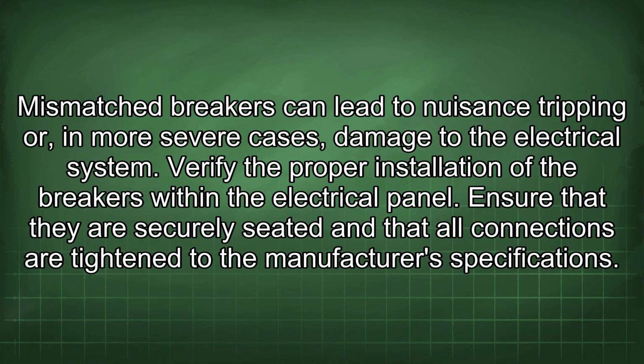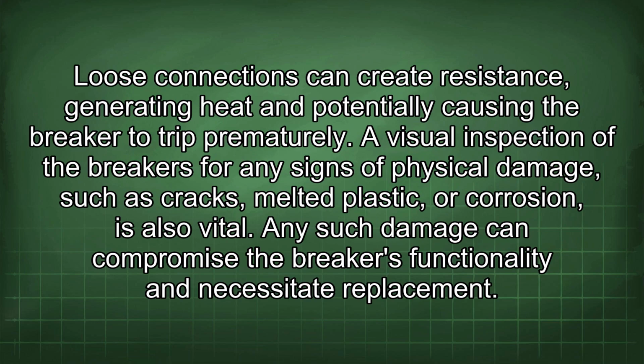Verify the proper installation of the breakers within the electrical panel. Ensure that they are securely seated and that all connections are tightened to the manufacturer's specifications. Loose connections can create resistance, generating heat and potentially causing the breaker to trip prematurely. A visual inspection of the breakers for any signs of physical damage, such as cracks, melted plastic, or corrosion, is also vital. Any such damage can compromise the breaker's functionality and necessitate replacement.